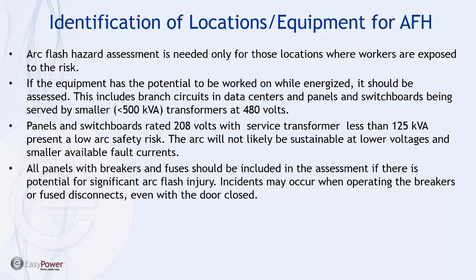Panels and switchboards below 208 volts with a service transformer of less than 125 kVA may be considered a low arc safety risk. They still need to be labeled because of the voltage level if they're going to be opened up. All panels with breakers and fuses should be included. If there's any potential significant arc flash injury, even a piece of equipment where the only operation is operating a circuit breaker with the panel closed, there's a potential for an arc flash event — and recognizing that is important for any electrician operating a circuit breaker.